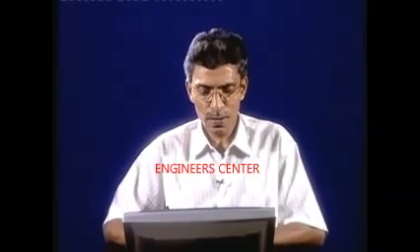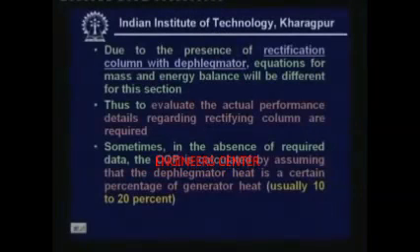If you neglect this, you find that there is a lot of water in the refrigerant circuit, and if you do not consider the presence of water, the system may not function properly and the calculations will differ from actual values. So, if you want to predict performance properly, you have to have the construction details of the rectification column and carry out this complicated analysis. In the absence of required data, the COP is calculated by assuming that the dephlegmator heat is a certain percentage of generator heat.